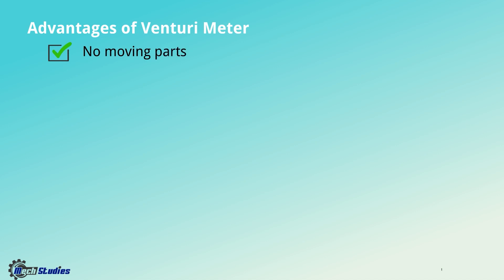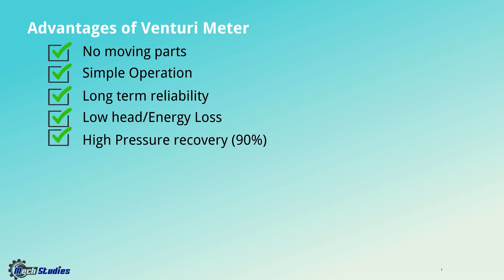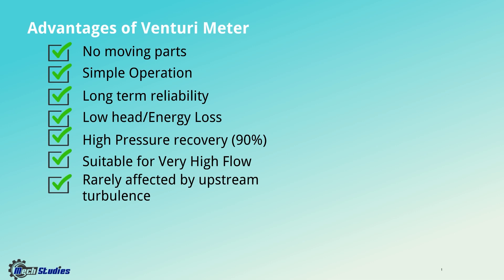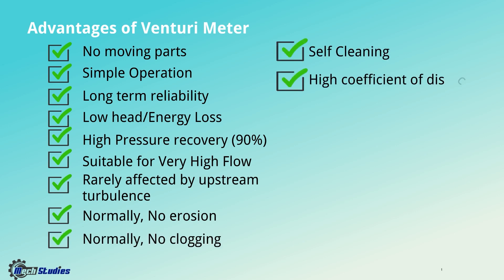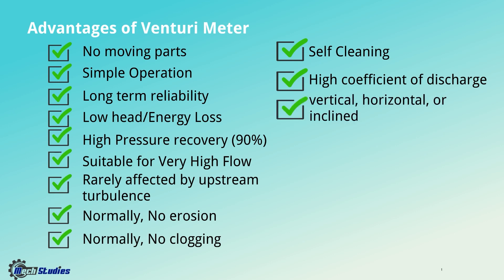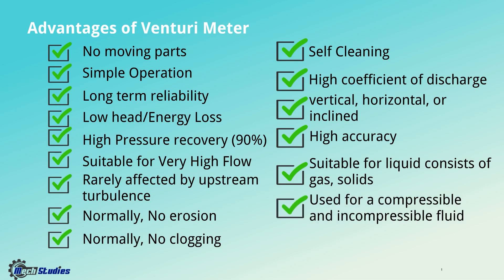Advantages of a Venturimeter include: no moving parts, simple operation, long-term reliability, low head or energy loss, high pressure recovery (around 90%), suitable for very high flow, rarely affected by upstream turbulence, normally no erosion, no clogging, self-cleaning, high coefficient of discharge, can be used in vertical, horizontal, and inclined configurations, high accuracy, and suitable for liquids containing gas or solids, as well as compressible and incompressible fluids.